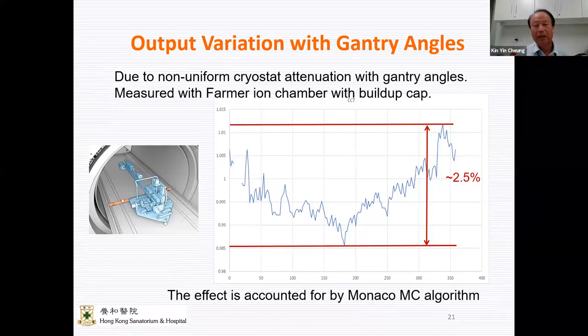Another parameter we need to measure is the output variation with gantry angle, because the cryostat of the MR system is non-uniform in terms of attenuation at different angles. So we measure the output every 2 degrees, and then use this output variation for beam modeling. The total variation is within 2.5%.